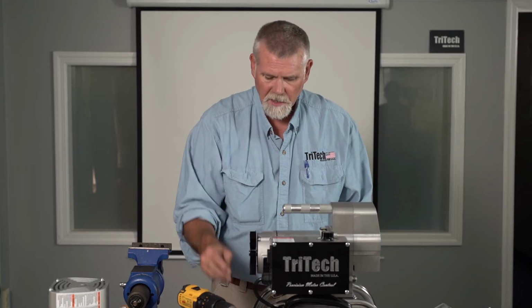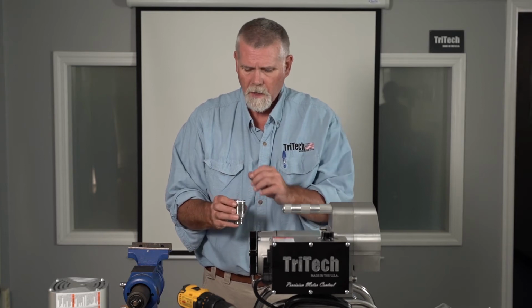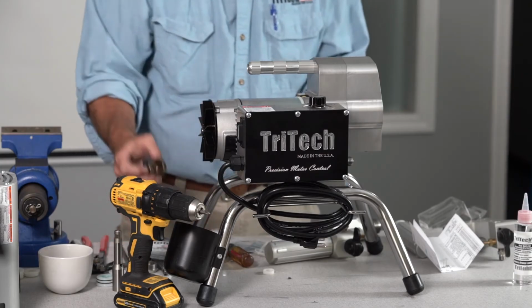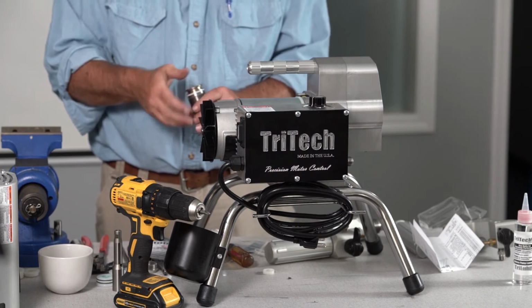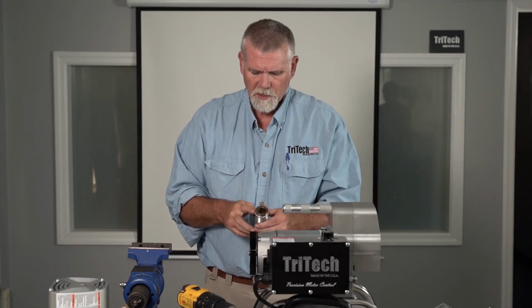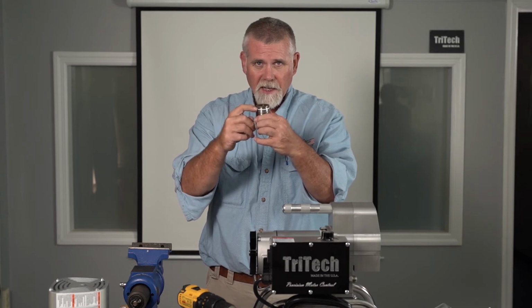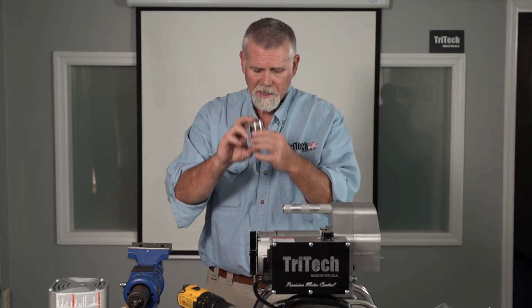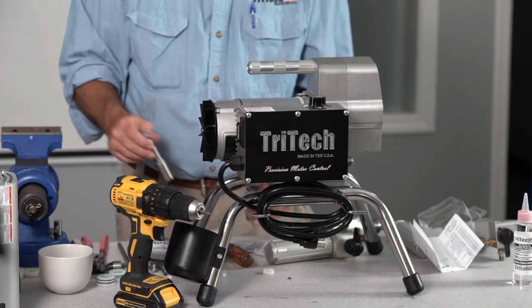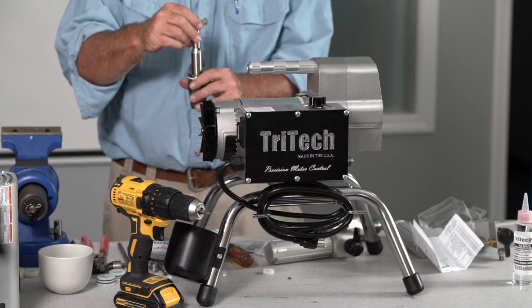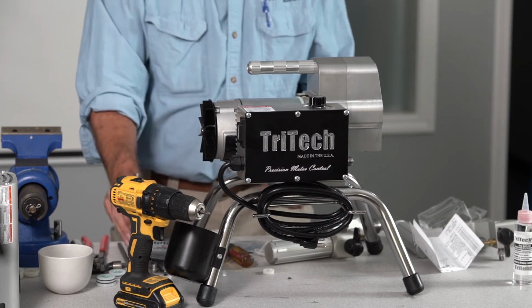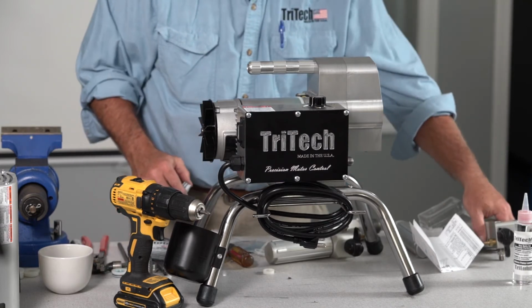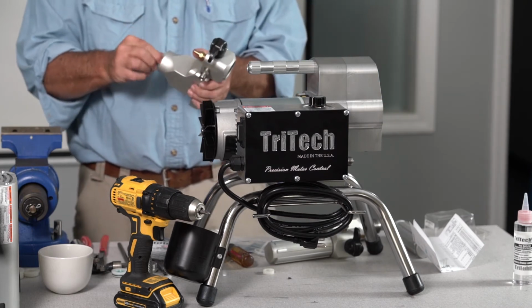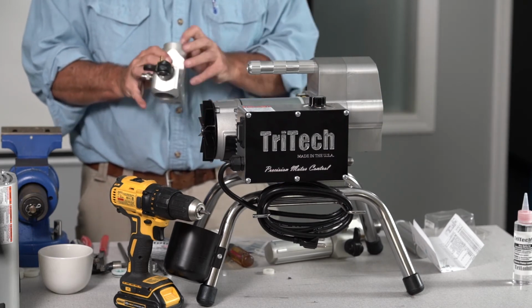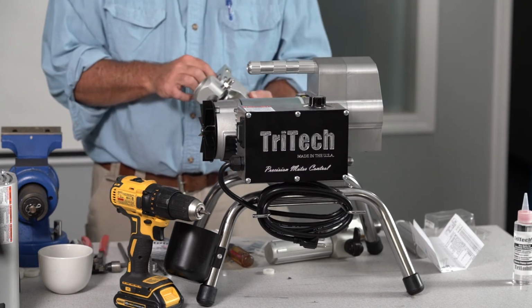We put our inlet seat. If one side is damaged, you can flip it over and use the other side. Our new inlet ball and our inlet ball retainer. That just pushes in. Remember I said this gap is there intentionally, so that's normal condition. Once that's done, then you take your piston and put it inside your foot valve housing, and you can then put your lower packing in place and put your upper packing in.